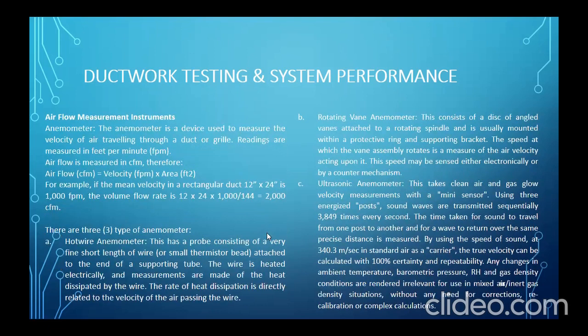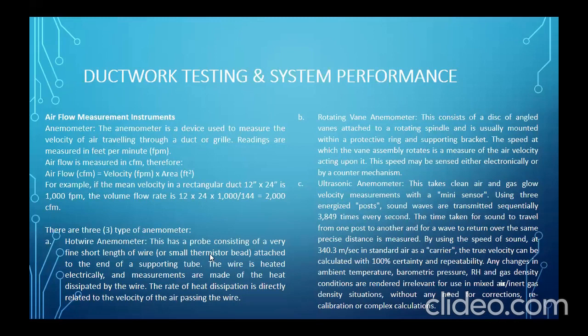So, airflow measurement, anemometer. The anemometer is a device used to measure the velocity of air traveling through a duct or grill. Readings are measured in feet per minute. Airflow is measured in CFM. Therefore, airflow is equal to velocity (FPM) times the area in square feet. For example, if the mean velocity in a rectangular duct of 12 inches by 24 inches is 1000 feet per minute, then the volume flow rate is 12 times 24 times 1000 over 144, which is 2000 CFM.